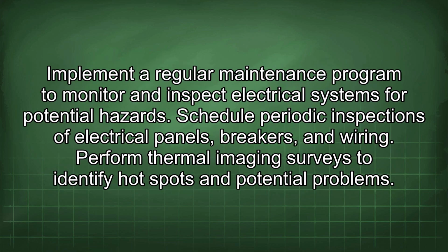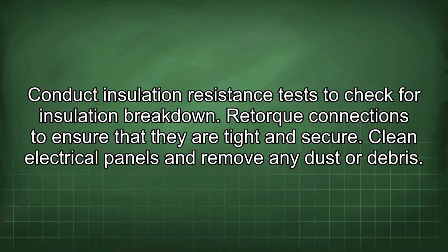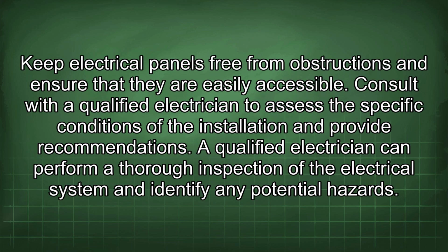Implement a regular maintenance program to monitor and inspect electrical systems for potential hazards. Schedule periodic inspections of electrical panels, breakers, and wiring. Perform thermal imaging surveys to identify hot spots and potential problems. Conduct insulation resistance tests to check for insulation breakdown. Retorque connections to ensure that they are tight and secure. Clean electrical panels and remove any dust or debris. Keep electrical panels free from obstructions and ensure that they are easily accessible.